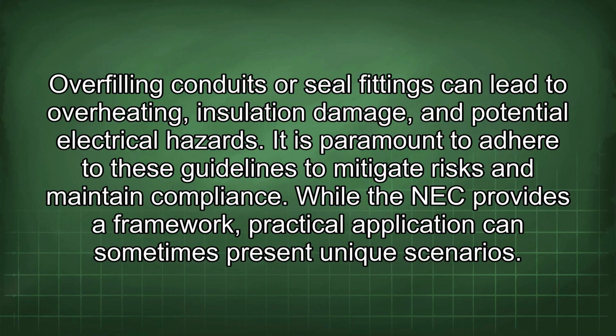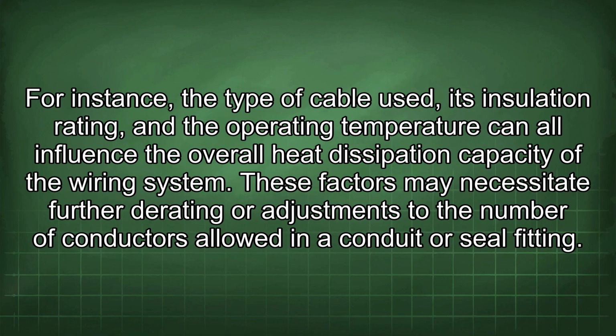While the NEC provides a framework, practical application can sometimes present unique scenarios. For instance, the type of cable used, its insulation rating, and the operating temperature can all influence the overall heat dissipation capacity of the wiring system. These factors may necessitate further derating or adjustments to the number of conductors allowed in a conduit or seal fitting.